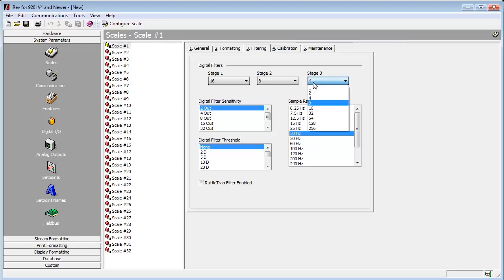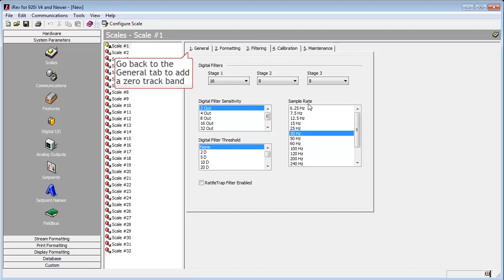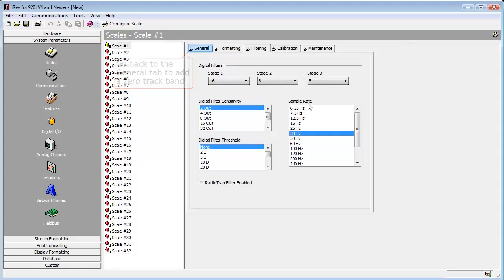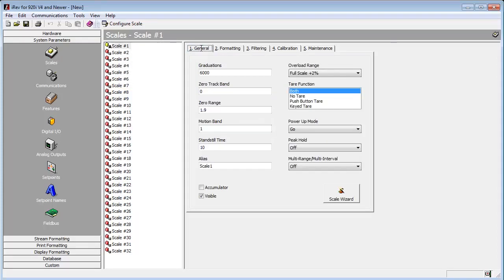In the event that we get some accumulation on the scale, we will set up a zero track band. This allows the scale to zero off accumulation without the need for human intervention. This is a useful feature in areas where snow or other matter accumulates, slowly adding weight to the scale.